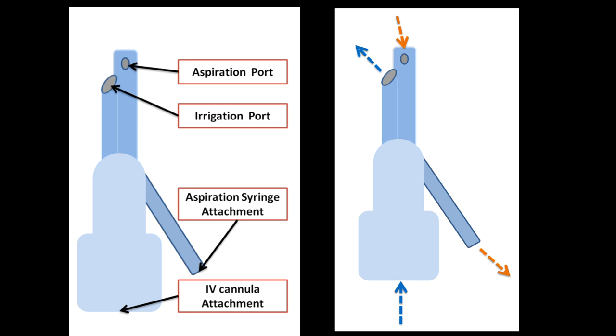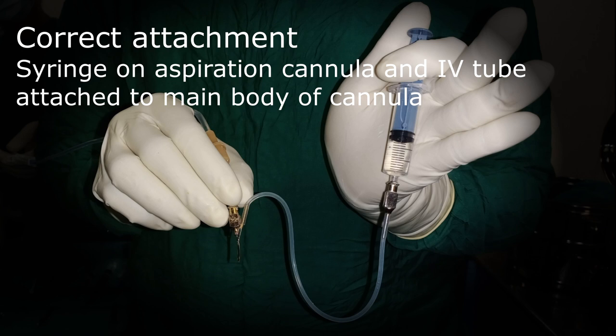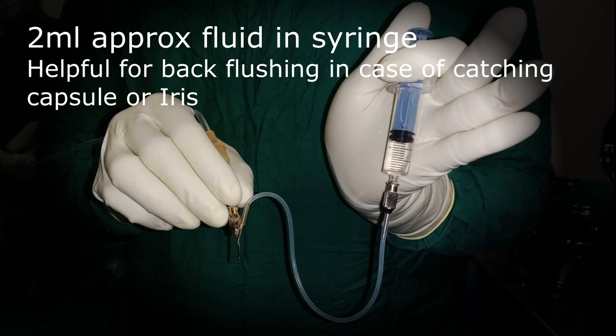Before starting cortex wash, let's check a few things. Number one is the attachment of the Simcoe, otherwise it will not work properly. The syringe should be attached properly on the aspiration tube and the IV tube should be attached to the hub of the cannula. Number two: take approximately two ml of fluid or air in the syringe, as it will be used for back-flushing.